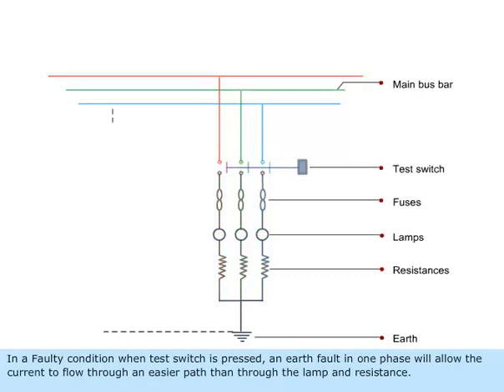In a faulty condition, when the test switch is pressed, an earth fault in one phase will allow the current to flow through an easier path than through the lamp and resistance.